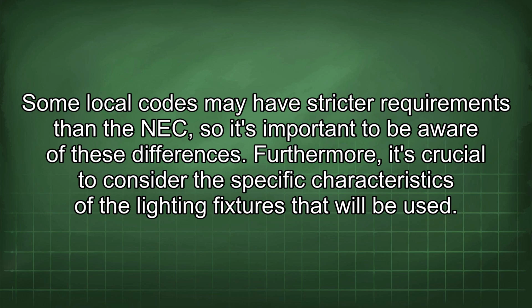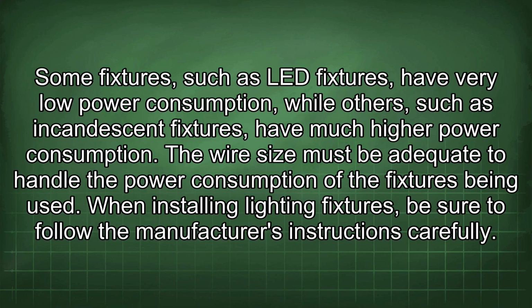of these differences. Furthermore, it's crucial to consider the specific characteristics of the lighting fixtures that will be used. Some fixtures, such as LED fixtures, have very low power consumption, while others, such as incandescent fixtures, have much higher power consumption. The wire size must be adequate to handle the power consumption of the fixtures being used.